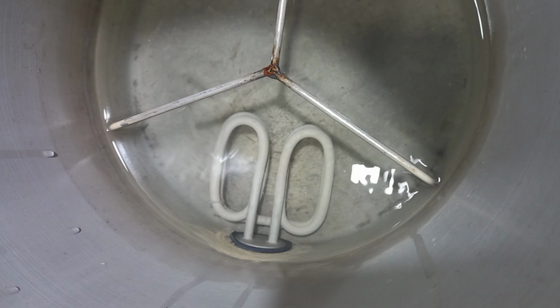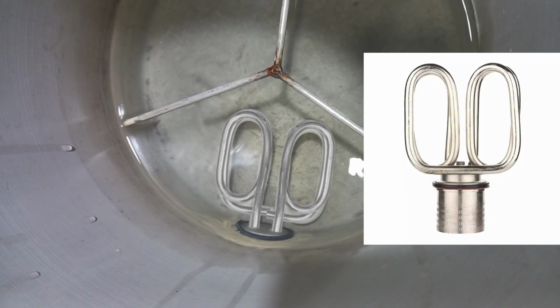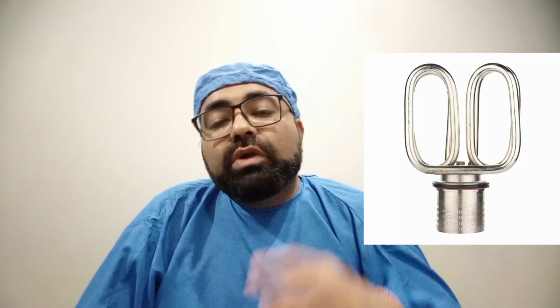And okay, doctors, finally, there is one additional use of distilled water in your dental clinic. Many times we see a white chalky substance developing inside our autoclaves and also on the heating coil. All these white chalky substances are minerals that got condensed by the boiling of our water. So if you are using distilled water for your autoclaving, the amount of scale formed inside your autoclave will be almost zero or very little. And when the scale inside your autoclave and on your heating coil is less, your heating coil will require less electricity and it can boil water faster.